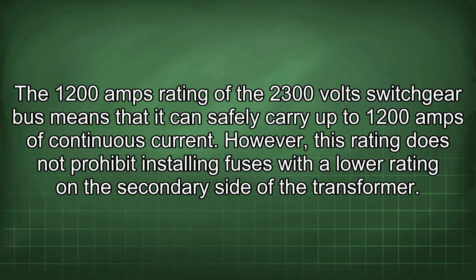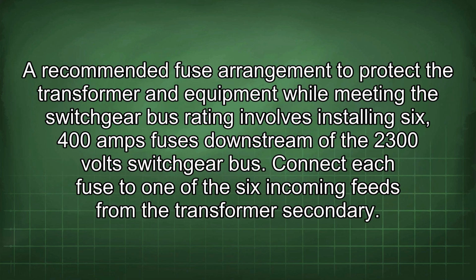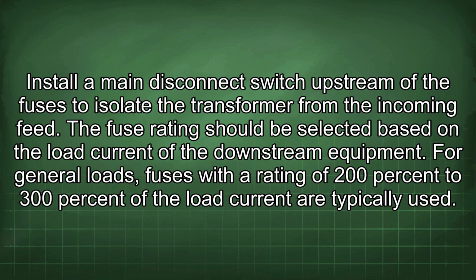of the transformer. A recommended fuse arrangement to protect the transformer and equipment while meeting the switchgear bus rating involves installing 6 400 amps fuses downstream of the 2300 volt switchgear bus. Connect each fuse to one of the 6 incoming feeds from the transformer secondary. Install a main disconnect switch upstream of the fuses to isolate the transformer from the incoming feed.